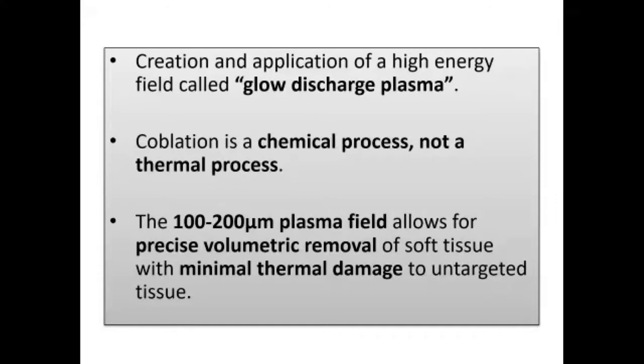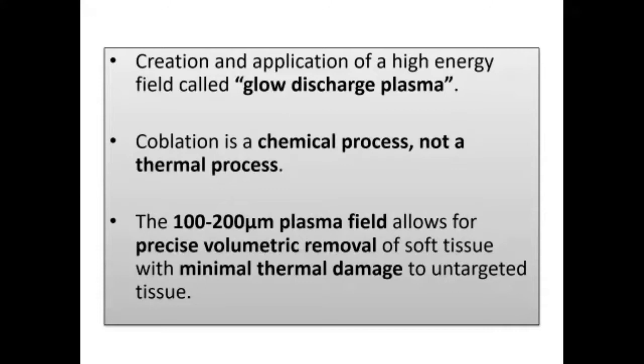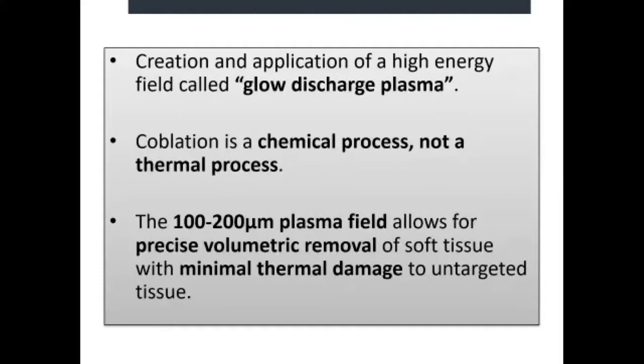An interesting point: coblation is not a thermal process — it's actually a chemical process. This glow discharge plasma is about 100 to 200 microns, which allows us to remove tissue layer by layer — what we call precise volume reduction. That's what we really enjoy when using coblation for tongue base or lingual tonsils.